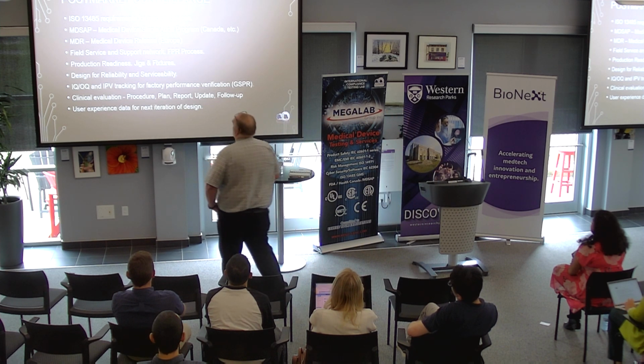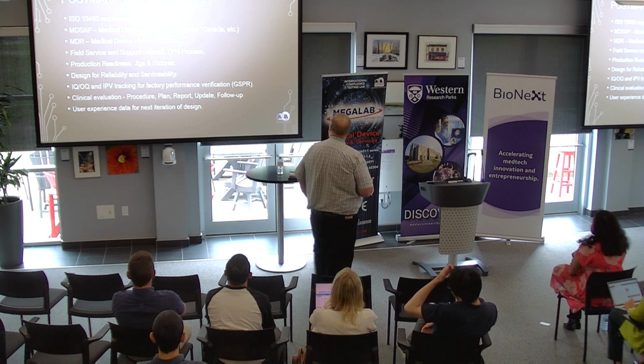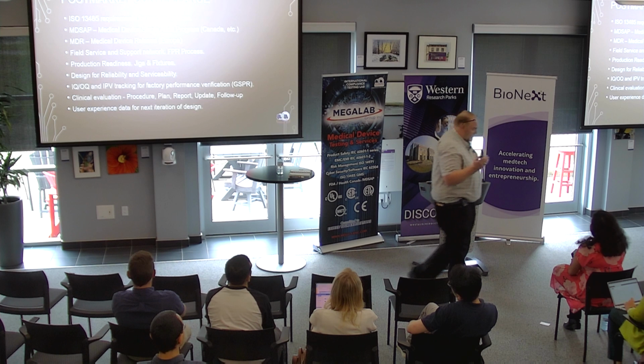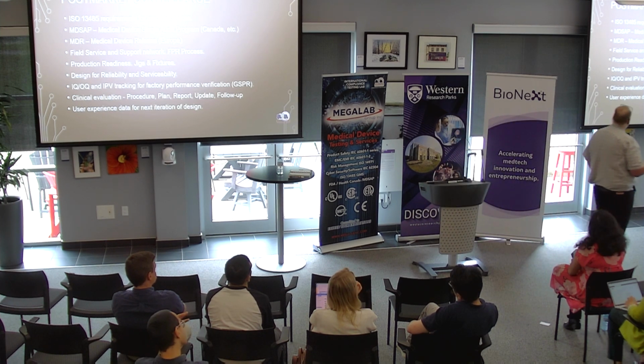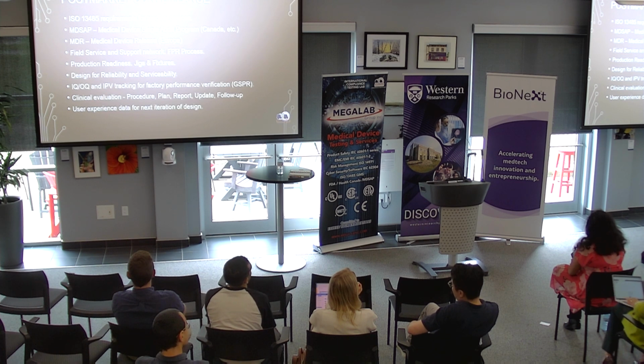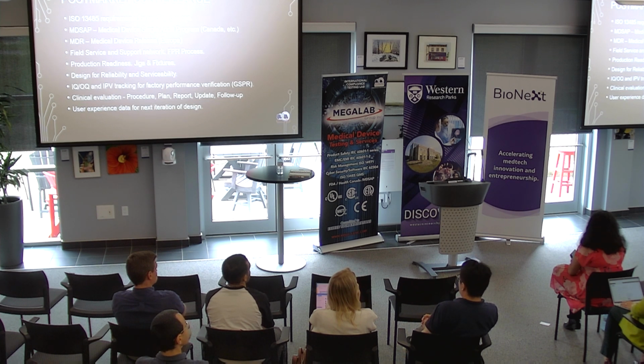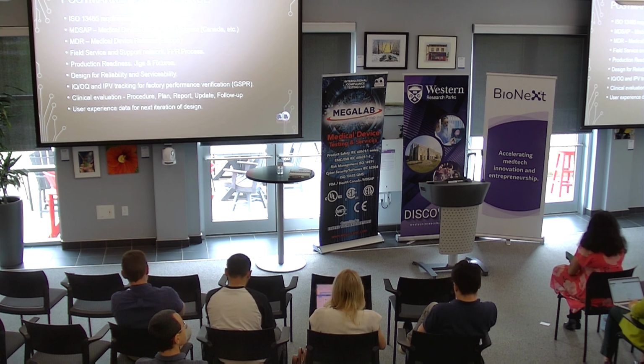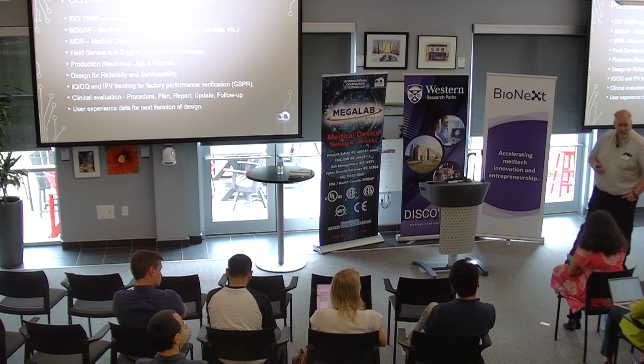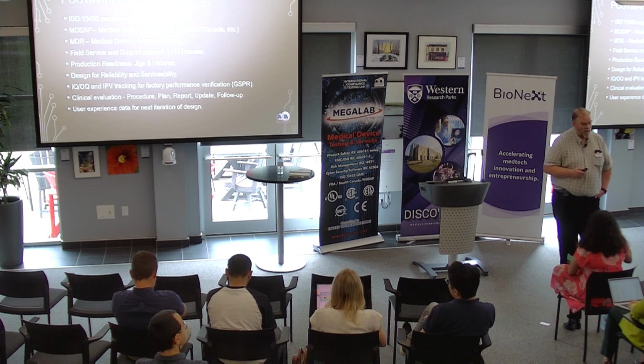So things you're going to look at: field service and support network. Your field problem reporting process is something you're going to have to concern yourself with quite a bit. Production readiness, jigs and fixtures, design for reliability and serviceability. That's something that people don't think a lot about, especially with high-tech products, is serviceability. Like I talked about before, your shipping crate shows up in Basel, Switzerland, and it's got screws everywhere. Well, you have to send a service guy out there to fix that product or ship it back. So you're going to have to take design for serviceability into consideration too, depending upon the complexity of your product. So just adding on that, now you've got to pay someone to go out there, and that adds $15,000.